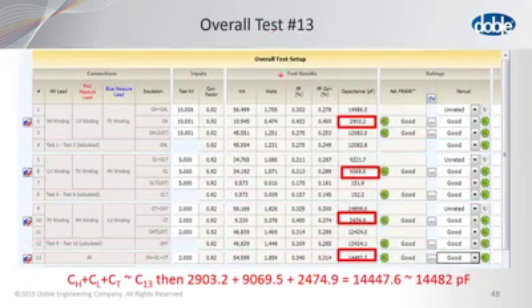And then the overall test, number 13, is what we call a check test. We add these 3 capacitances together, and in this particular case, it's that number right there, and then we compare it with the number that we measured. And notice this is very, very close. It's about 40 parts in 14,000. And if it's too far away, we'll flag that something might have been done wrong in one of these 4 tests, or some of those 4 tests.